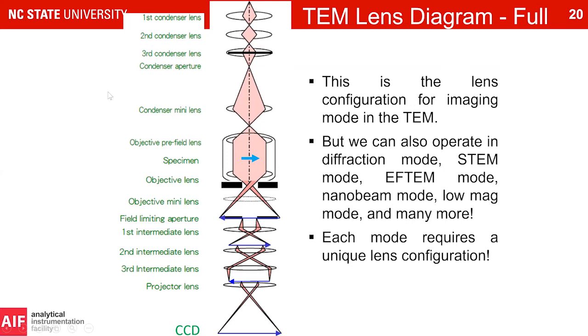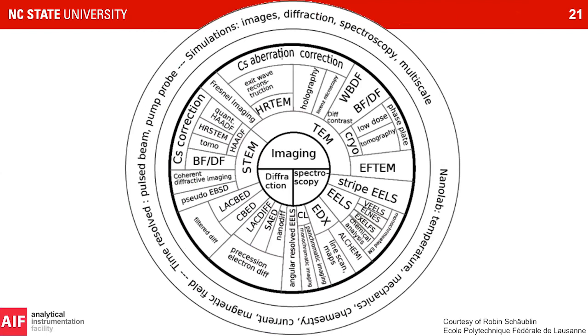Ray diagrams of a TEM show quite a few lens components — about half the elements are still missing here. We have so many lenses to increase the versatility of the microscope. In the old days, dedicated TEMs and dedicated STEMs couldn't do both. Today, microscopes are designed so you can operate in TEM mode, STEM mode, energy-filtered mode, form nano-beams, do very low-mag imaging, and a huge number of configurations — all because we have full control over all different lens elements.